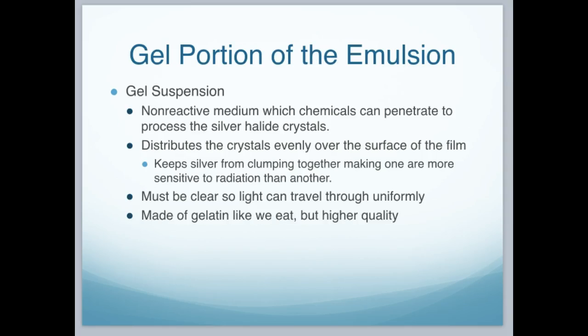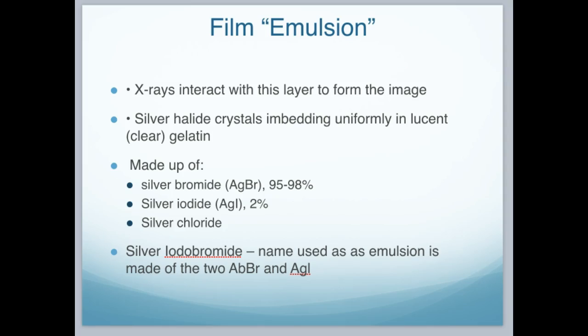There's a gel suspension that holds this emulsion. It's a non-reactive medium through which the chemicals can penetrate and process the silver halide crystals. The gel is inert and non-reactive. It distributes the crystals evenly over the surface of the film, and this keeps the silver from clumping together, making one area more sensitive to radiation than others. It must be clear so light can travel through it uniformly, made of gelatin like we eat but just a higher quality, more dense. X-rays interact with this layer to form the image.